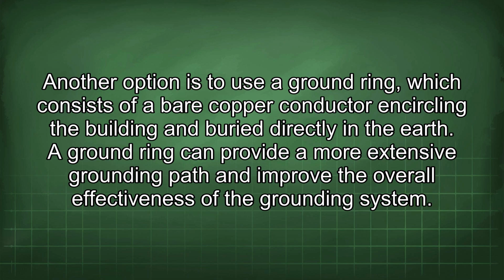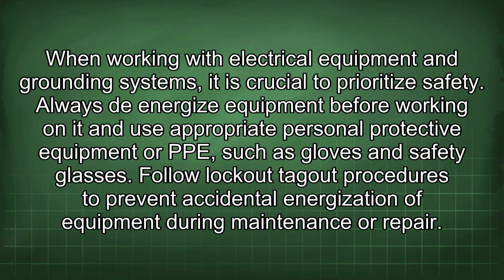Another option is to use a ground ring, which consists of a bare copper conductor encircling the building and buried directly in the earth. A ground ring can provide a more extensive grounding path and improve the overall effectiveness of the grounding system. When working with electrical equipment and grounding systems, it is crucial to prioritize safety. Always de-energize equipment before working on it and use appropriate personal protective equipment, or PPE, such as gloves and safety glasses. Follow lockout-tagout procedures to prevent accidental energization of equipment during maintenance or repair.